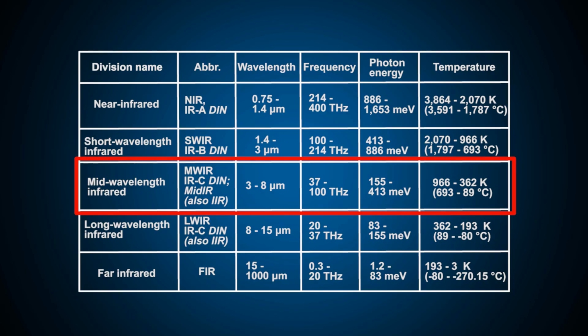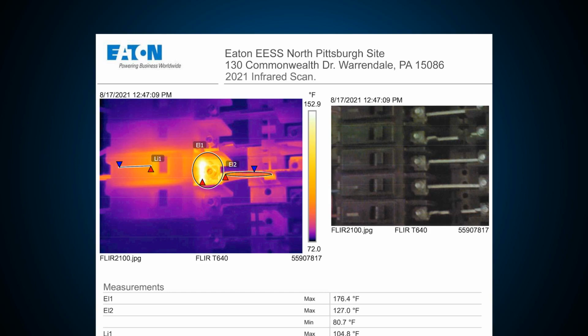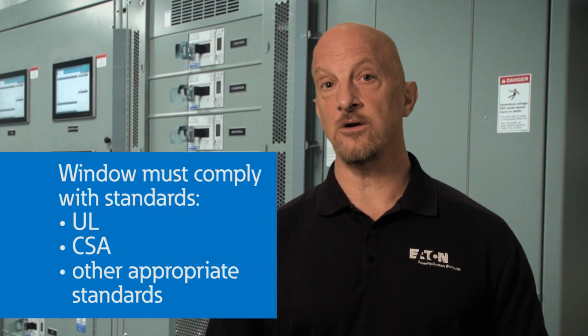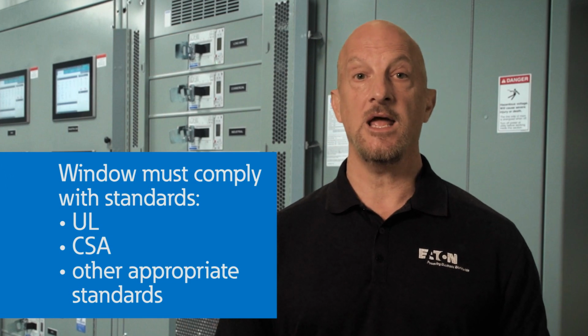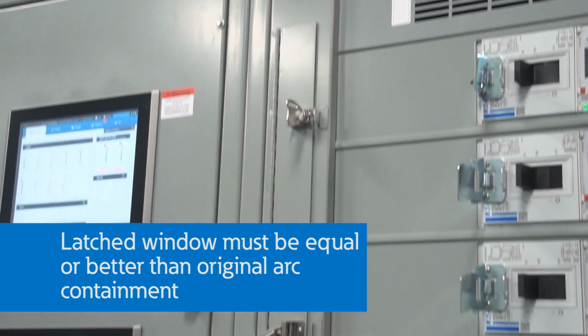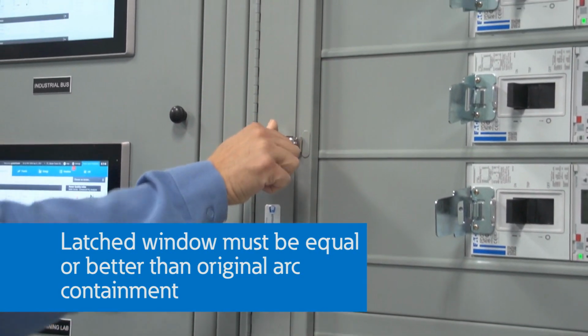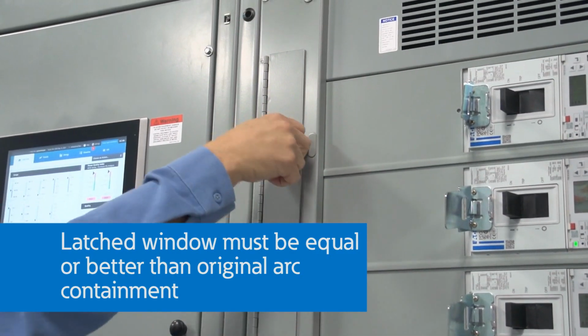Next, you should always use a visually clear IR window or panel to allow for visual inspection of the energized compartment, as well as infrared capable with any IR camera, shortwave, medium wave, long wave. This allows you to take digital photos while you're doing IR scanning. This will really help you to match the physical location with the IR images for reporting and analysis purposes. In addition, the construction of the IR window or panel should be in compliance with UL, CSA, and other applicable standards. It should also be approved and tested for arc containment. In other words, by putting this window or panel in your equipment, the arc flash containment of the original equipment should not be diminished if this cover is closed and properly latched.